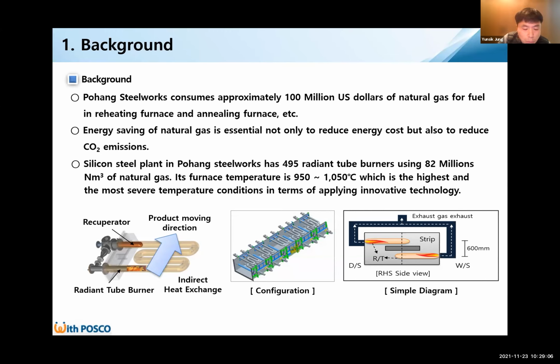The silicon steel plant in Pohang Steelworks has 495 radiant tube burners using 82 million normal cubic meters of natural gas. Its furnace temperature is 950 to 1050 Celsius degrees, which is the highest and most severe temperature condition in terms of applying innovative technology. We chose the most severe conditions for the experimental and field circumstances to prove energy savings and its robustness.